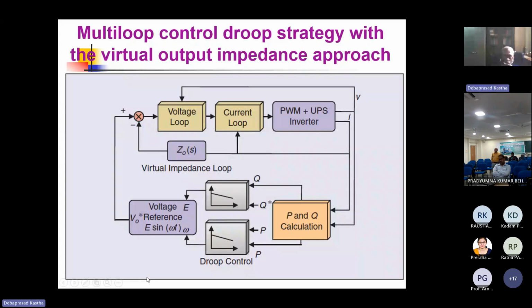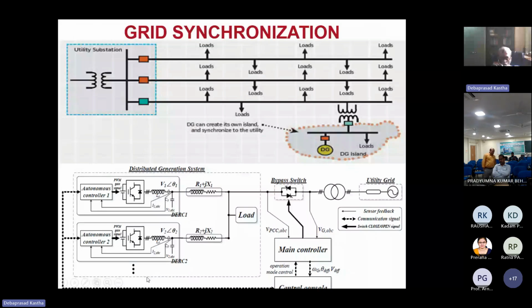The next job is grid synchronization. As I said, a DG may operate synchronously with the main grid, or it can disconnect. It is done using a bypass switch. There are reasons why you want to disconnect. This is called islanding, and there are many islanding techniques also. But once it disconnects, it has to generate its own voltage. Suppose after some time you want to connect back to the grid, so a synchronization procedure is needed.